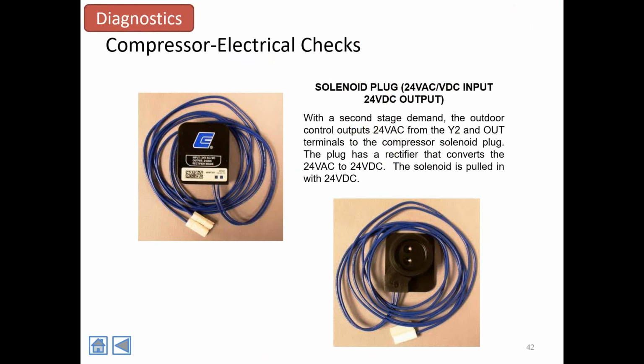Compressor electrical checks on this unit. We have a solenoid on our two-stage compressor, and it is 24 volts DC going to the solenoid. This device here that you see is a plug, but it also has a rectifier built into it. So we're going to send 24 volts down to it, and then the compressor is going to get DC voltage to change it over from single stage to two stage.